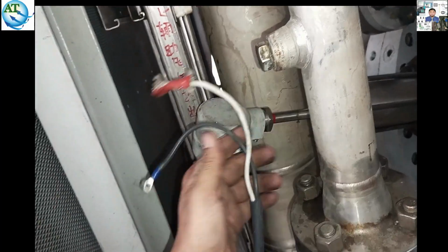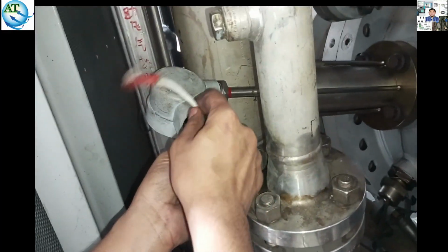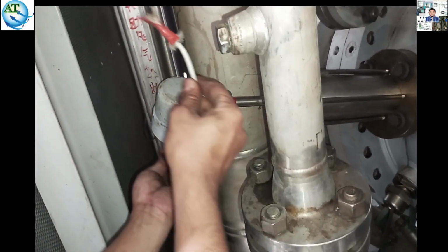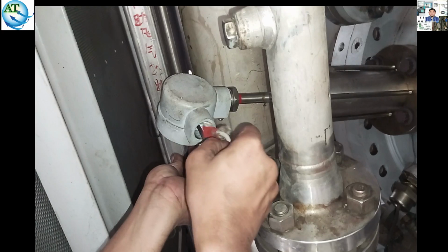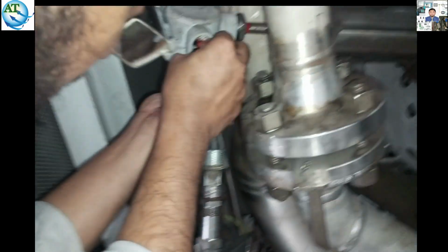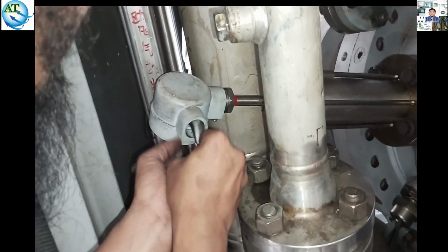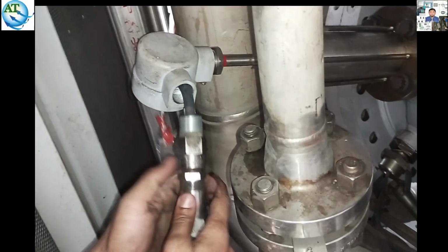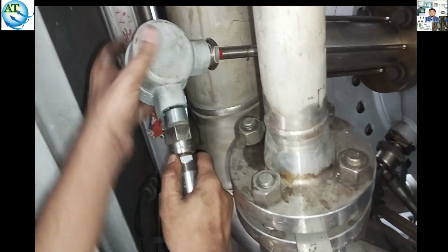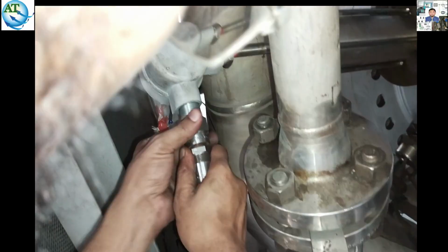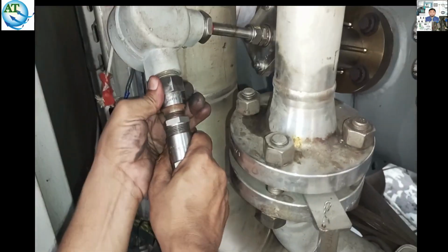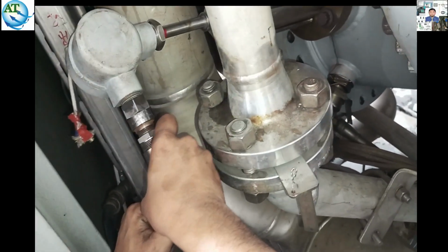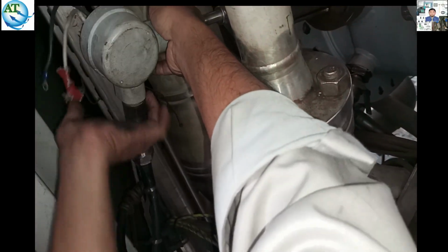That means the supply is coming from the igniter transformer. It is a 6 kV transformer that you are using. That means the 3-phase or single-phase 220 V is converted to 6 kV to ignite the burner and start the turbine. That means it is actually using 6 kV supply to the igniter rod. So we are connecting this cable. After completing this, we try to start the turbine.